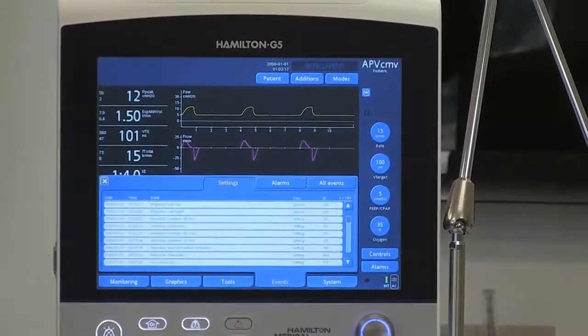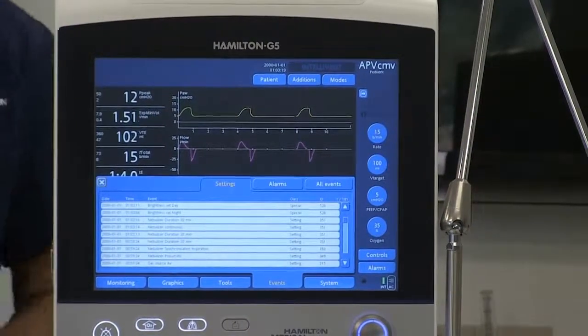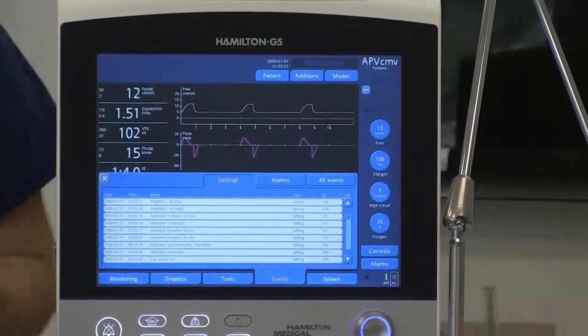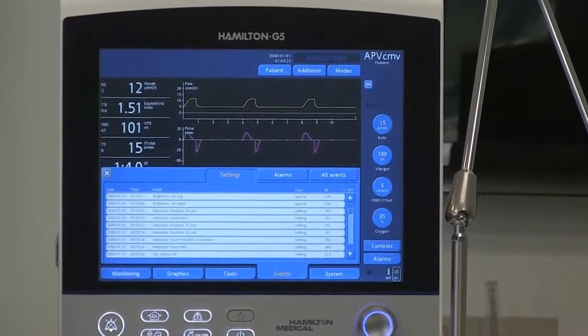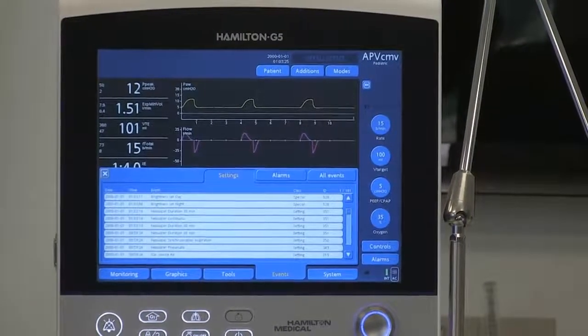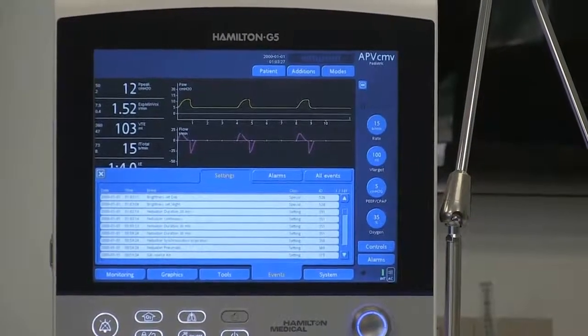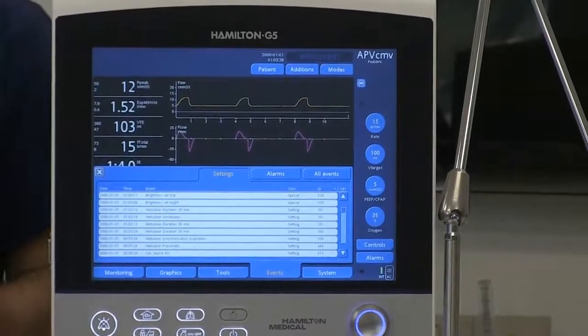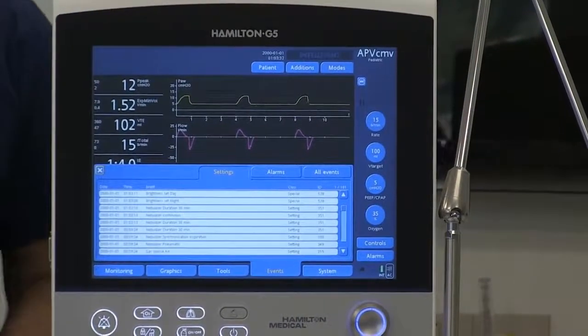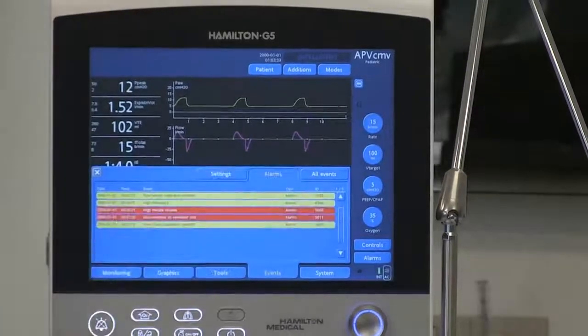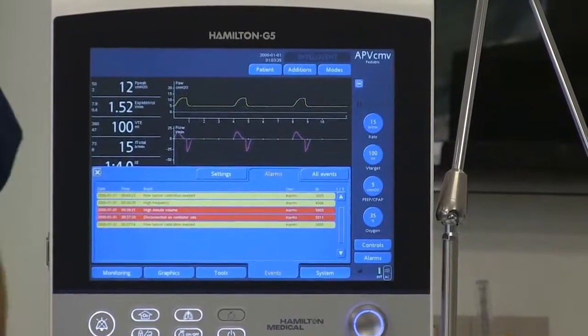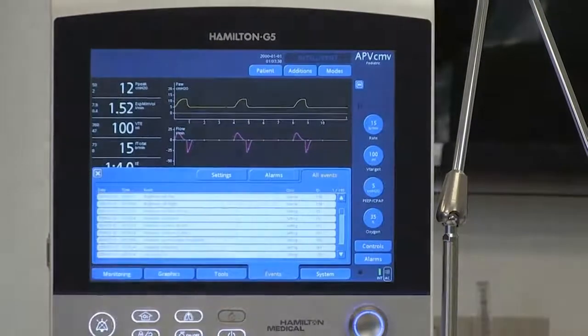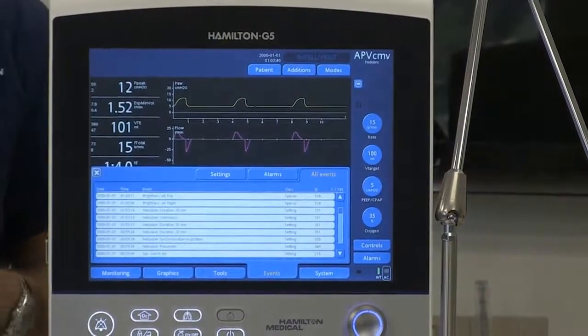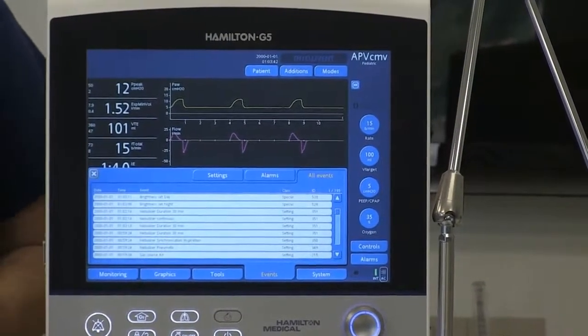In the events section, this is where you'll get anything that is done to the vent, including alarm silences, FiO2 boosts, or manual breaths, as well as alarm parameter changes and setting changes. The alarm section gives you your alarm history, and the all events section gives you all alarms and setting changes.